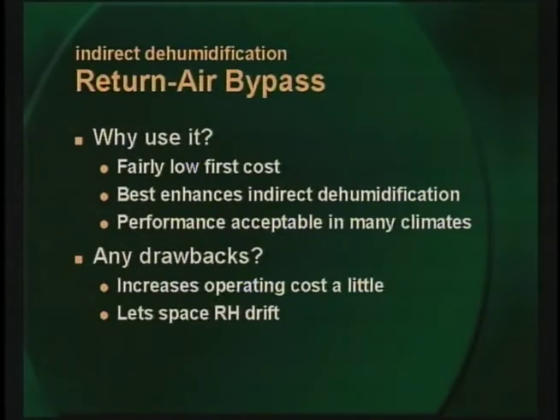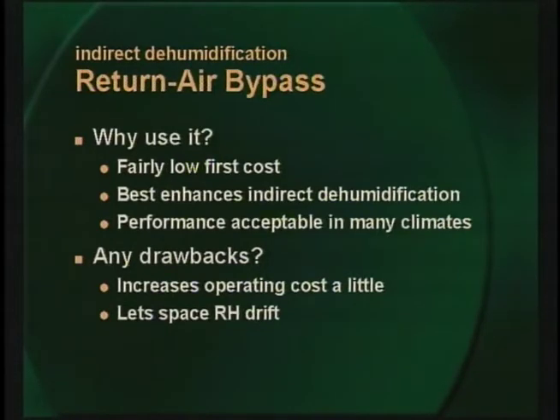That's still above our target value of 52%, but it's a definite improvement over mixed air bypass. In many climates and at many loads, return air face and bypass provides adequate indirect control of space relative humidity. Return air bypass does a better job than mixed air bypass simply because all of the moist outdoor air passes through the coil, allowing relatively dry return air rather than relatively moist mixed air to mix with and reheat the cold air leaving the coil. Return air face and bypass is available factory installed with most catalog and custom air handlers, and it limits space relative humidity better than mixed air face and bypass at both sensible design and latent design conditions.